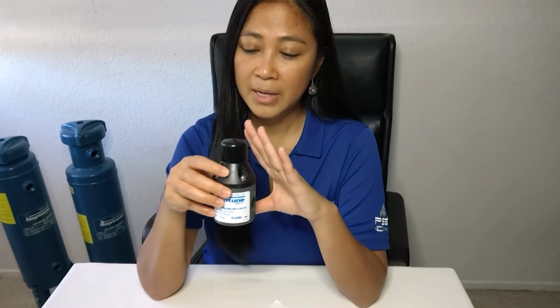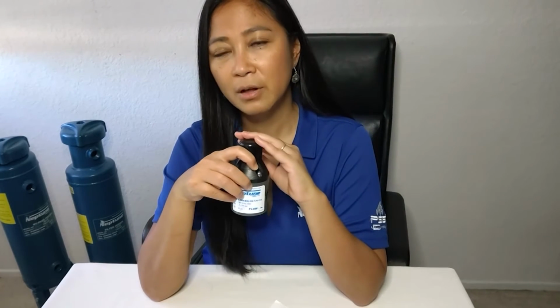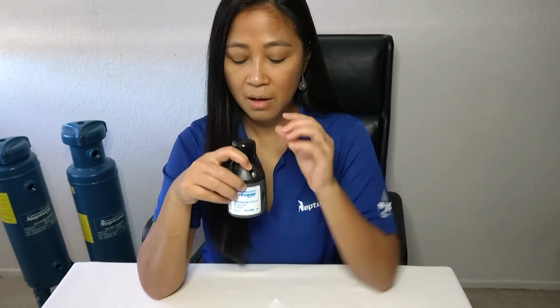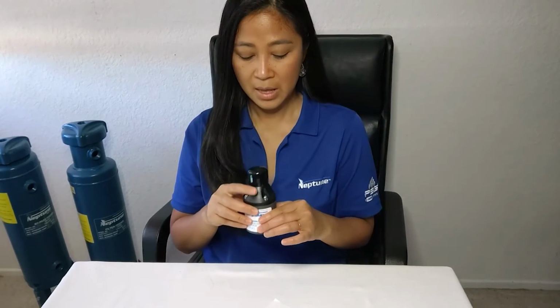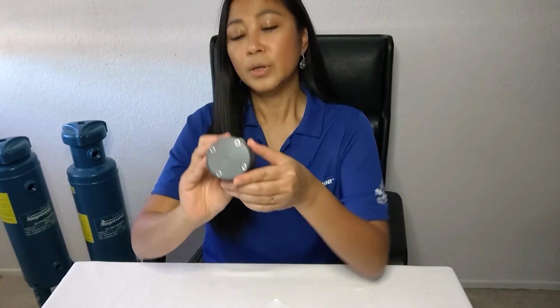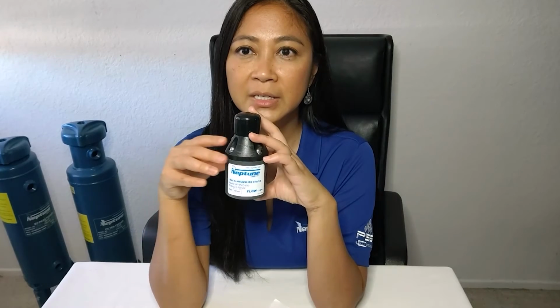To install this, you install the back pressure valve in the discharge line and see the flow indicated on the bottom, meaning the flow is going that way. You could also see that on the label, the flow is going that way. So this is the inlet and right here is the outlet.